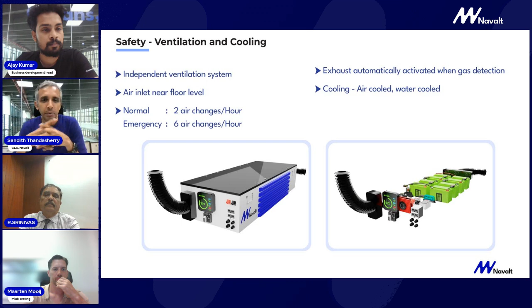Some aspects from our own practices — there is, of course, a class requirement on ventilation, and a class requirement for gas detection based on chemistry. But our practice is to try to position the gas detection inside the battery itself, more or less where the exhaust side is, because that is quicker to detect rather than monitoring the whole compartment. This is just from our experience.